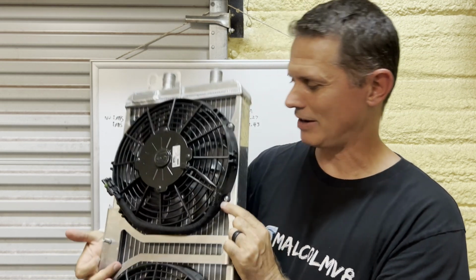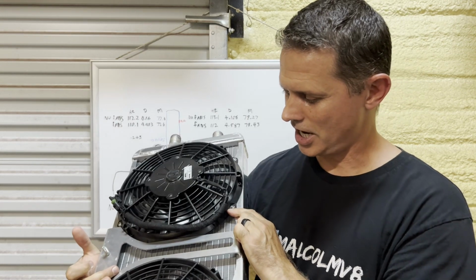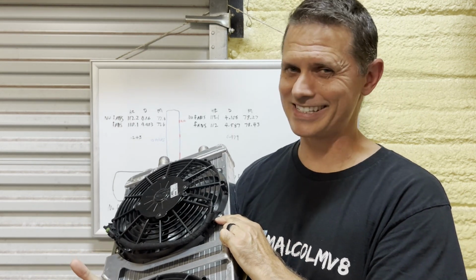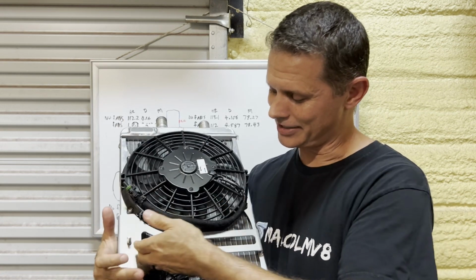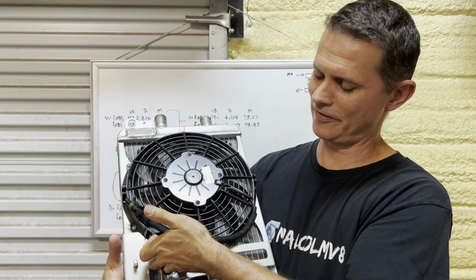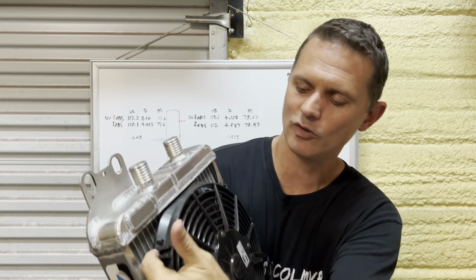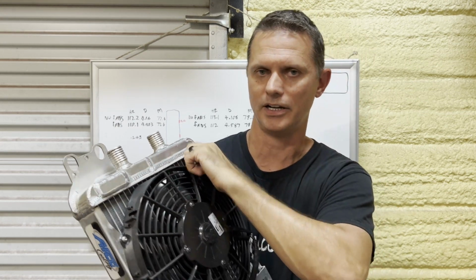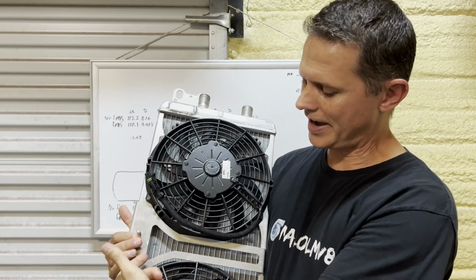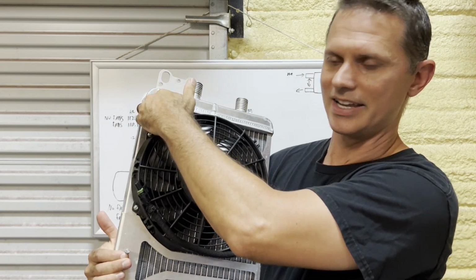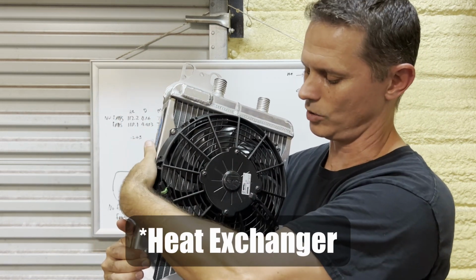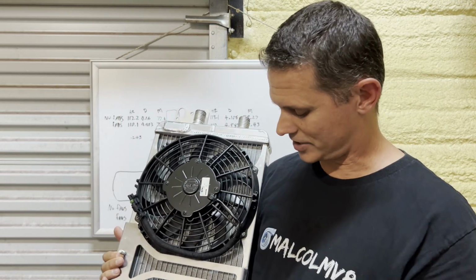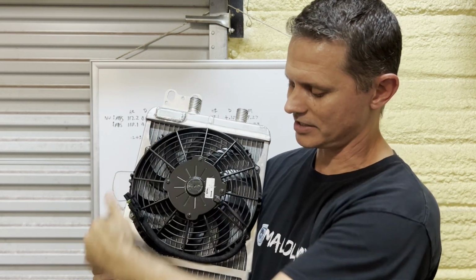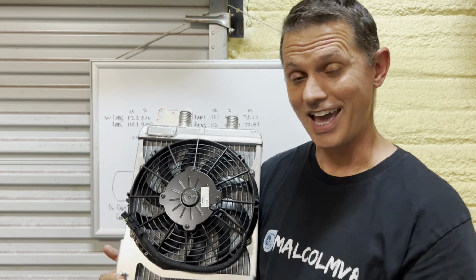However, there's one major thing we haven't pointed out — look at how these fans are mounted onto this heat exchanger. I'll call it complete garbage. Look, I can literally fit my fingers underneath the fan, there's that much space. That means the fan is just sucking air from the sides instead of pulling it through the intercooler, and to make it worse, there's no shroud forcing suction across the whole thing.